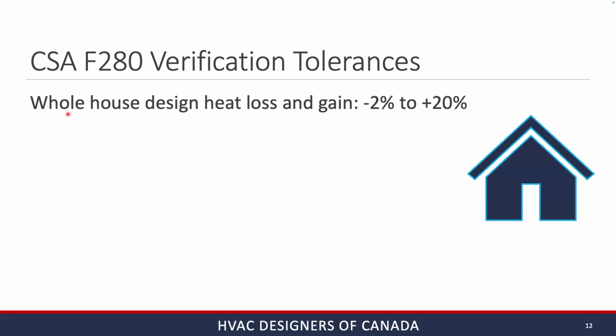They decided that for the whole-house part of your load calculations, results should never be less than 2% below the correct answer, and never more than 20% above. Below, because you don't want the house to get cold or hot in summertime; above, because of equipment sizing thresholds and triggering a larger piece of equipment that's not necessary.